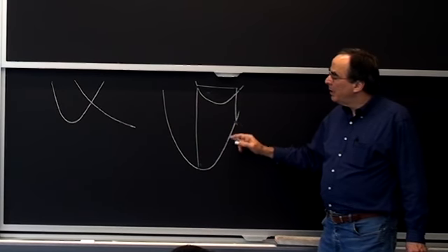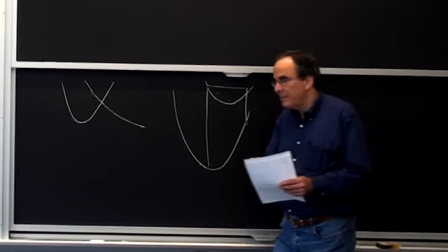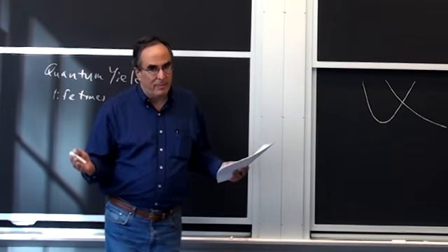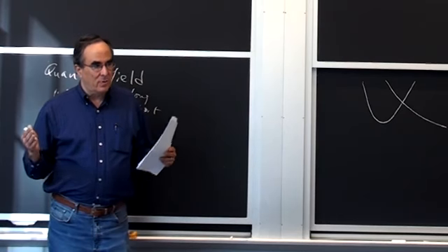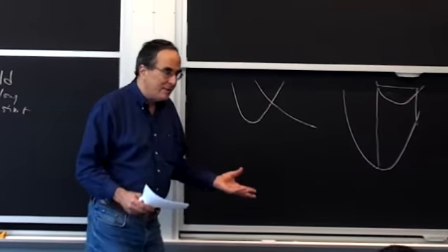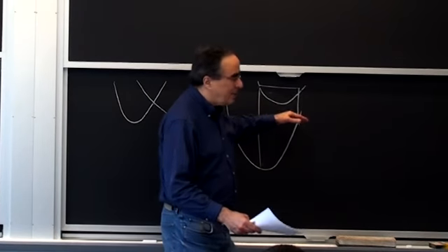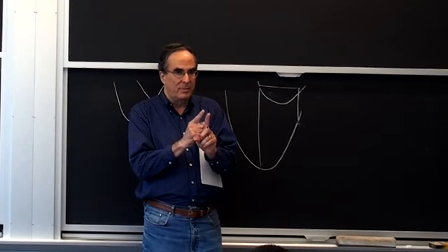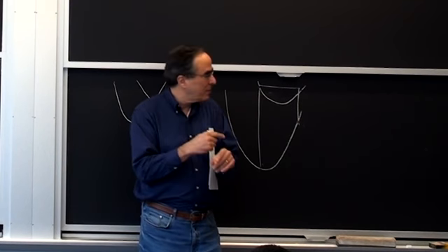Usually these effects of the sensitivity range of the photomultiplier are quantitative. They don't make a line disappear, but they make the intensities of transitions that occur in the same region of the spectrum be different from what you expect.